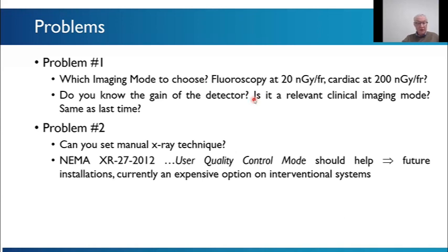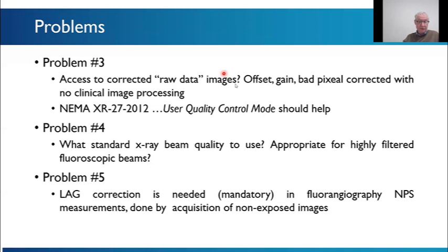Which mode are you in? I mean, do you measure fluoroscopy or cardiac or series imaging? Do you know the gain of the detector? You probably don't. Is the gain the same as it was last time? I mean, the detector has got lots of different modes, and you hope that it goes in the same mode each time you go in to measure. And our experience of it in normal imaging is that it does, and DR imaging and mammo. But in fluoro, it's more dynamic. I know that acquisition has got a lower gain than the fluoro. Okay. Can you set manual technique? We've discussed that already. Do you have access to raw data?